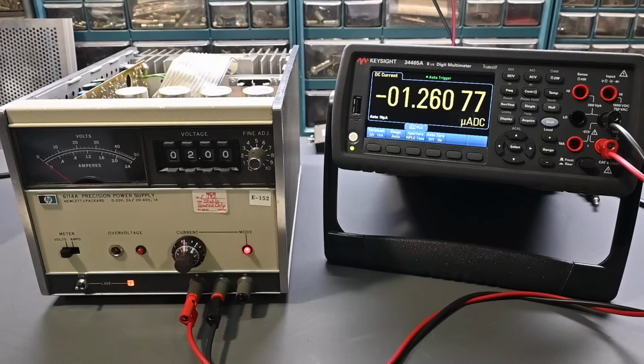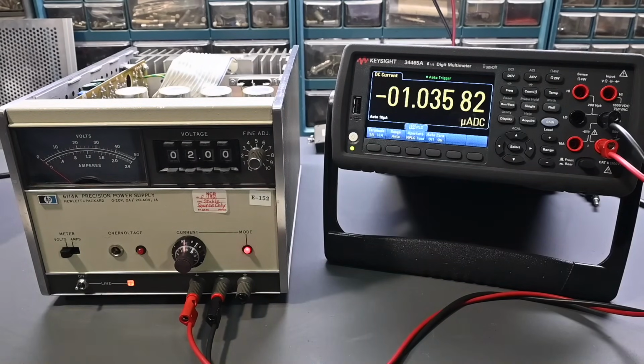What you're supposed to do is across that 0.1 ohm resistor, use a differential voltmeter and make the adjustment for plus minus 10 microvolts across that resistor. So if you use Ohm's law, then you would know the current flowing through that resistor, and essentially you're adjusting for a very, very low value. Because I don't have that very precision type of resistor and that very low value, what I'm doing is just measuring the output current directly on the digital multimeter. Well, if you use Ohm's law, 0.1 ohms and 10 microvolts, so plus minus 10 microvolts is what they specify, so the current could be negative. But again, 0.1 ohms and 10 microvolts is equivalent to 100 microamps.